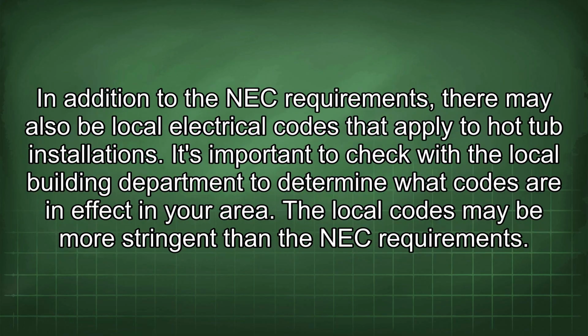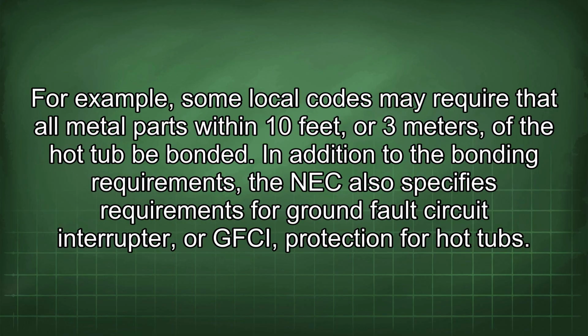In addition to the NEC requirements, there may also be local electrical codes that apply to hot tub installations. It's important to check with the local building department to determine what codes are in effect in your area. The local codes may be more stringent than the NEC requirements. For example, some local codes may require that all metal parts within 10 feet or 3 meters of the hot tub be bonded.